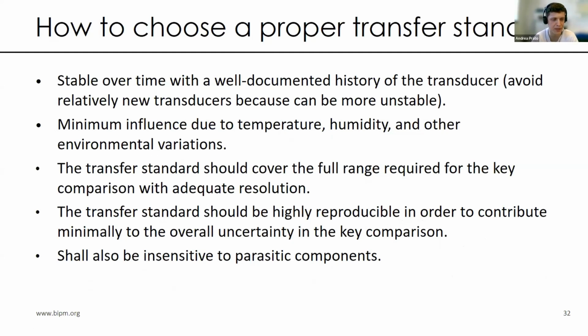So given these influences and given the solutions for these influences in order to minimize them, which are the main parameters we should take into account to choose the proper transfer standard? So first of all, we should choose stable transfer standards over time with possibly a well-documented history of the transducer. So it is not indicated to use a new transducer because it can be more unstable, and we do not have a well-documented history of the transducer itself. We should also choose a transfer standard that has minimum influence due to ambient conditions like temperature, humidity, and so on.